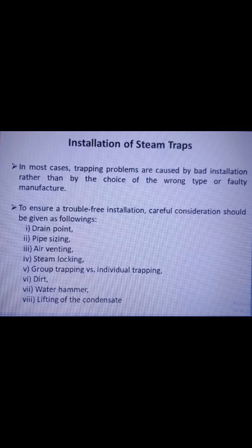Fifth one is group trapping versus individual trapping. It is tempting to try and save money by connecting several units to a common steam trap, as this is known as group trapping. However, it is rarely successful since it normally causes waterlogging and loss of output. It follows that the pressure at the drain outlet of a heavily loaded unit will be less than in the case of one that is slightly or properly loaded.